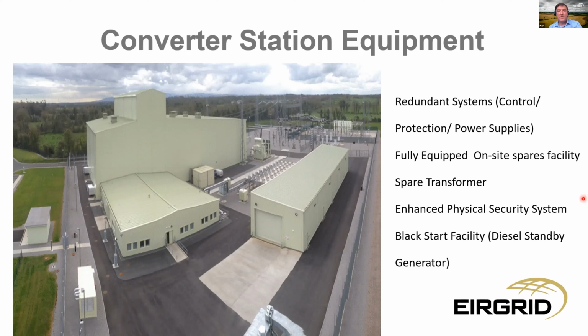The asset is maintained on an annual basis in what's best described as an 84-hour pit stop. Motivated specialist crews review and inspect the assets and replace components as required. So it's important to have a fully equipped on-site spares facility located here. With the strategic importance of the asset, a transformer fault is mitigated with an upfront capital cost of a strategic spare. This minimizes unavailability of the asset in such events and improves business continuity. The spare transformer is located here.